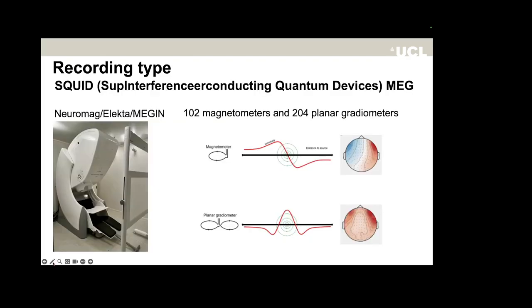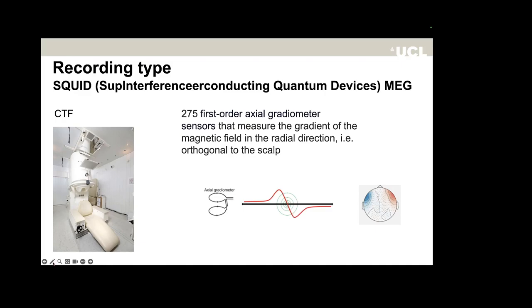The sensors inside an MEG system can be of two types: magnetometers or gradiometers, with gradiometers further divided into axial or planar types. For example, the Neuromag system has 102 magnetometers and 204 planar gradiometers. Magnetometers provide the best signal and are more sensitive to deep brain sources, but also more sensitive to competing magnetic noise. Gradiometers are much better at noise reduction. It is important to know which sensor type you are using when interpreting spatial topographies, as axial gradiometers, planar gradiometers, and magnetometers give slightly different topographies.